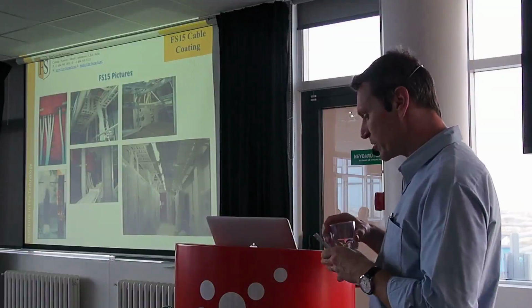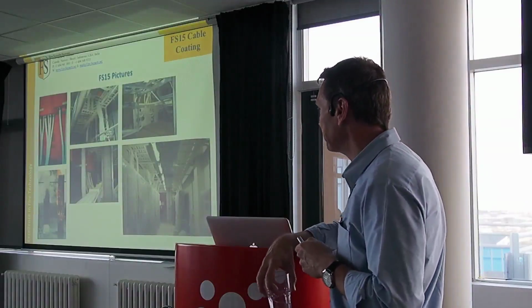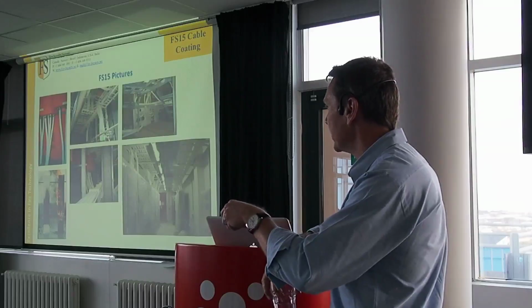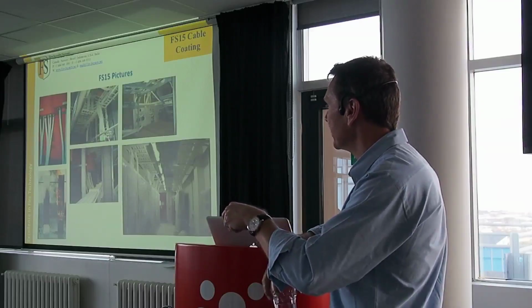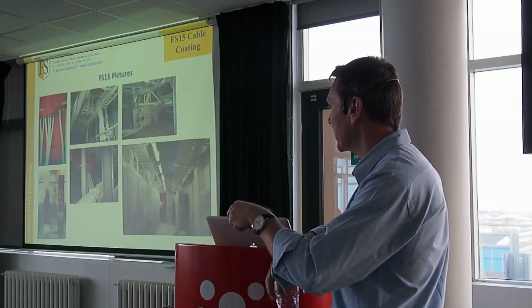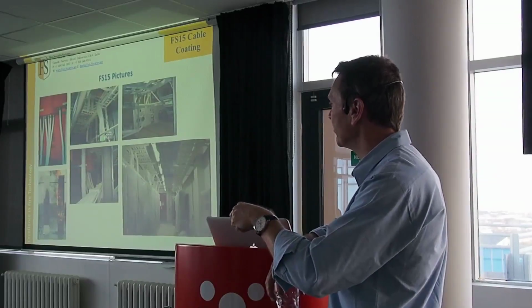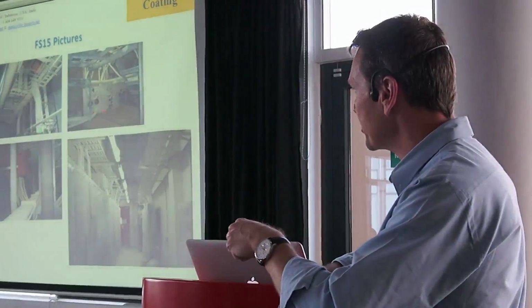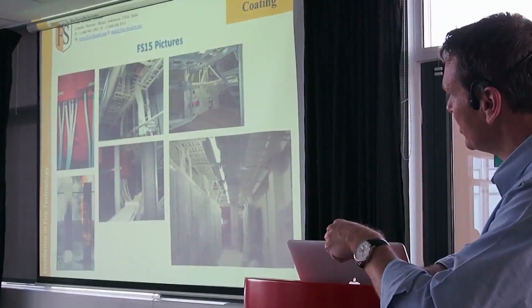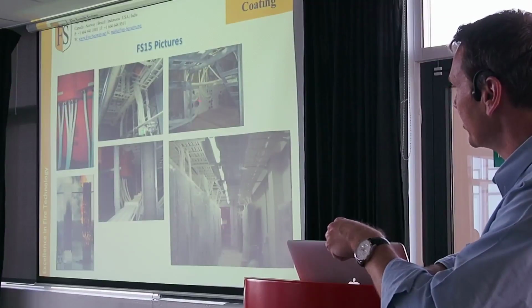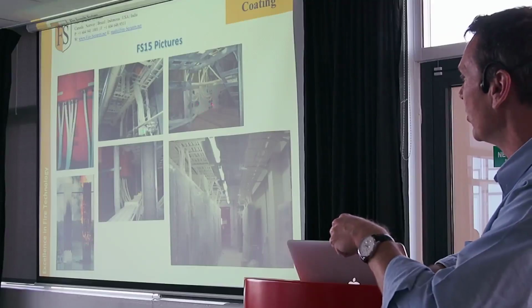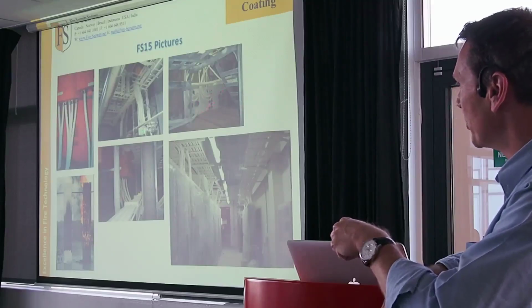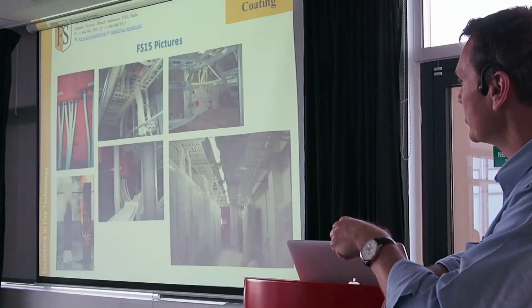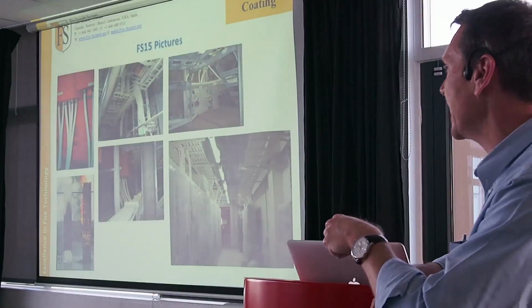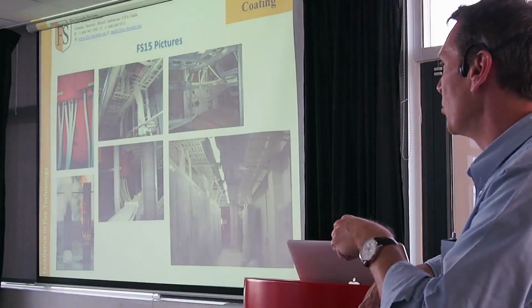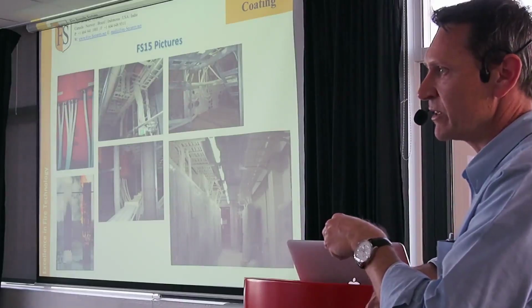So some types of applications that we have here, all being industrial, are bottom-fed switchgear, large areas, open areas that people aren't willing to lose their cables and don't want flame spread to other areas. Basement areas. Notice that these are direct-fed conduits in a cable gallery. We've kept them open. A lot of the time these are sealed up, but there's no point to sealing them because of the water ingress. And most of the penetration seals on the market don't have pressure and head for water behind them. So you have to, unfortunately, let the water come out.